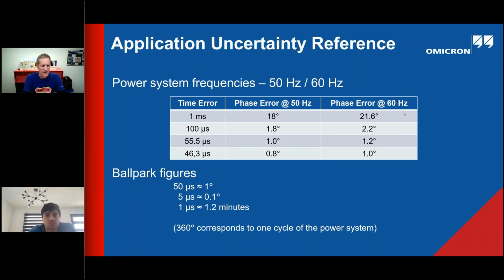In the end, we get 1 electrical degree in the power system with about 50 microseconds time uncertainty, and so on. So 5 microseconds is 0.1 degree, and that's already something. There are not too many devices which can really measure phase angle to 0.1 degree uncertainty. That's really already a challenge.